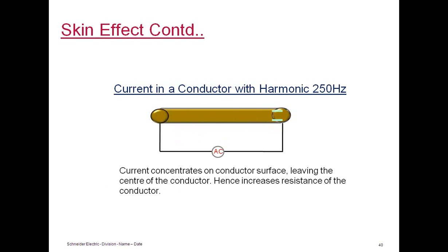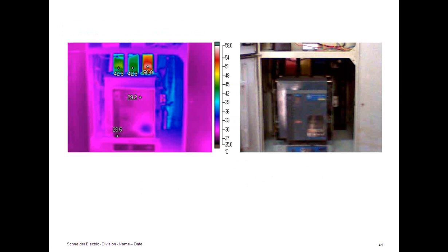So the 5 times increased resistance is significant enough to create heat loss in the conductor. This is a thermal image we took at one of the shopping malls where we had a lot of fancy lighting systems. Apparently, we had this fancy lighting on only one phase, line number 3. We told the customer to verify that the RMS value of current was equal in all 3 lines. But only in line 3 we had significant harmonic current. So in a couple of hours we found line 3 had a temperature of 56 degrees centigrade. We did verify the terminations and everything was intact, but because of harmonics we have more temperature on one of the phases here.